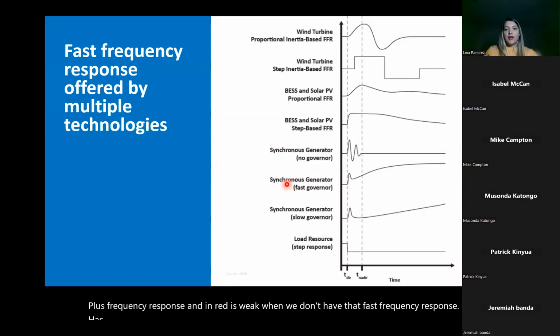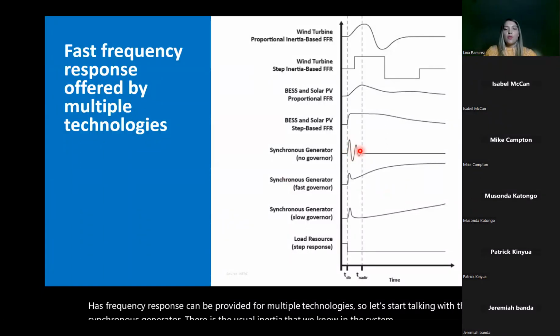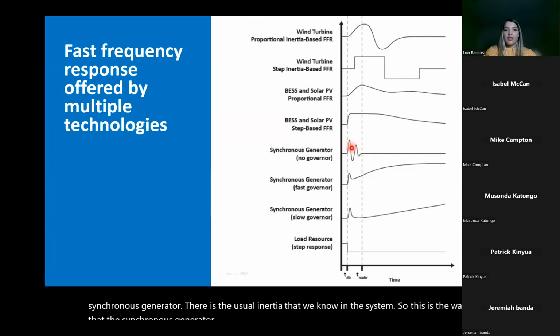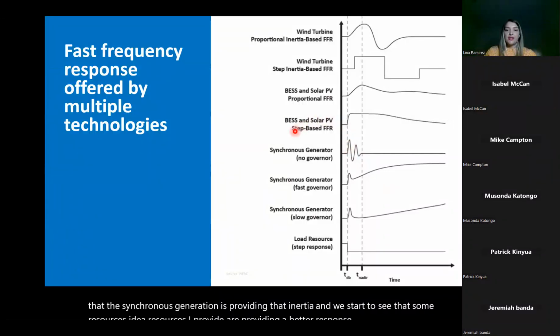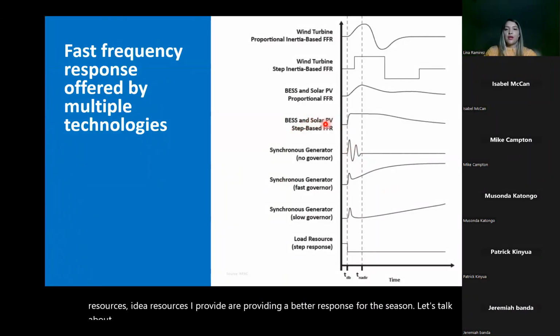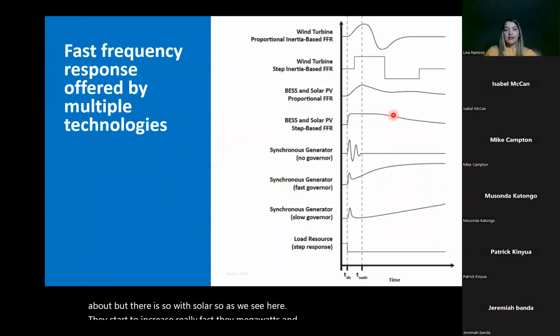Fast frequency response can be provided by multiple technologies. Let's start with the synchronous generator, which is the usual inertia that we know in the system. This is the way that synchronous generation provides that inertia. And we start to see that some IBR resources provide a better response for the system. Let's talk about batteries. With solar, as we see here, they increase megawatts really fast, and they maintain that response for the time that the system needs.